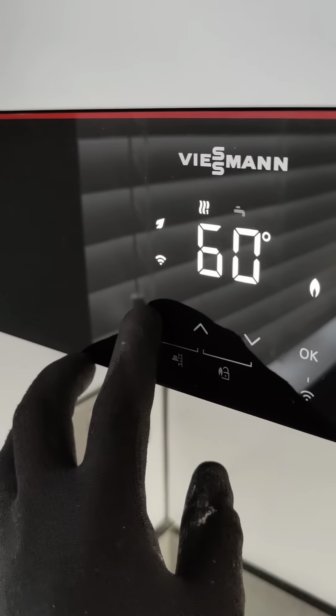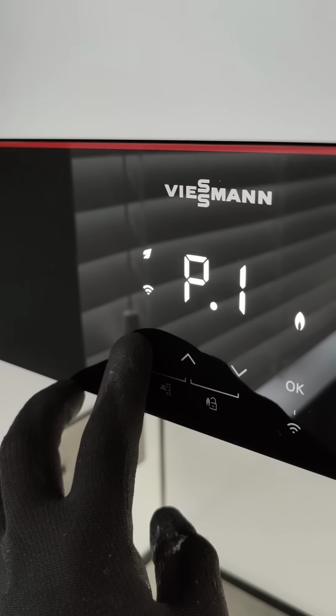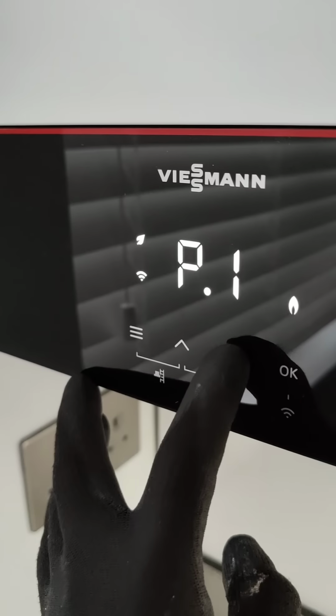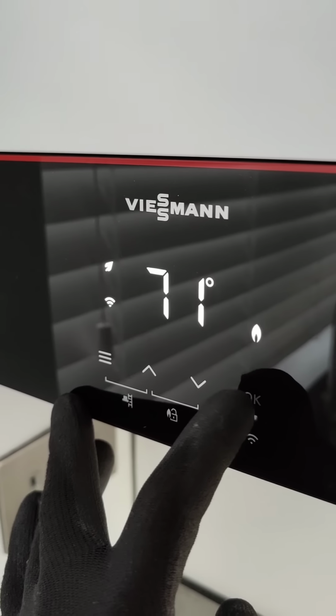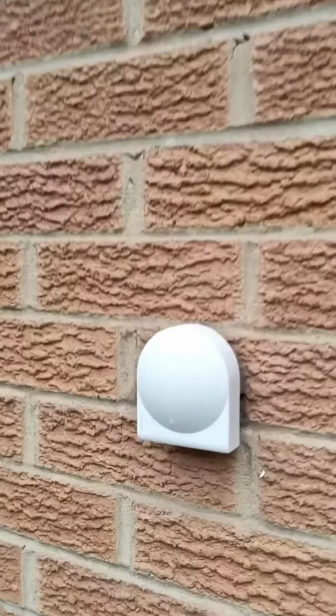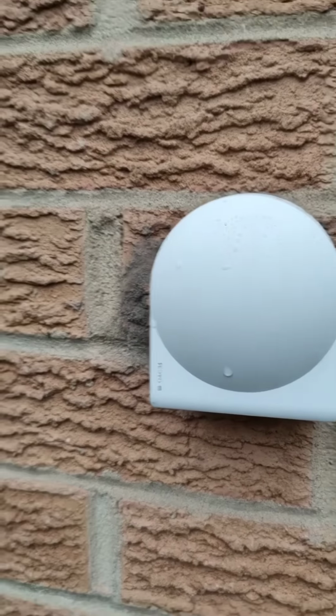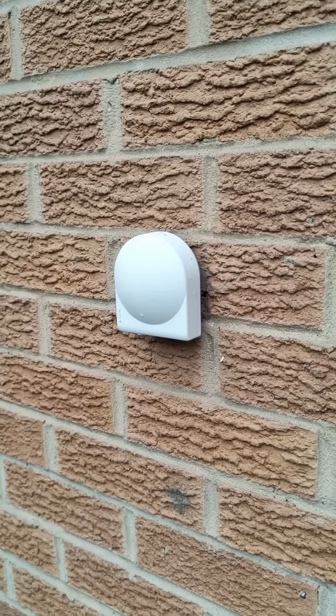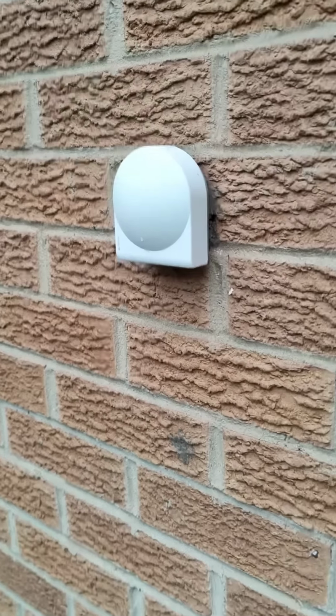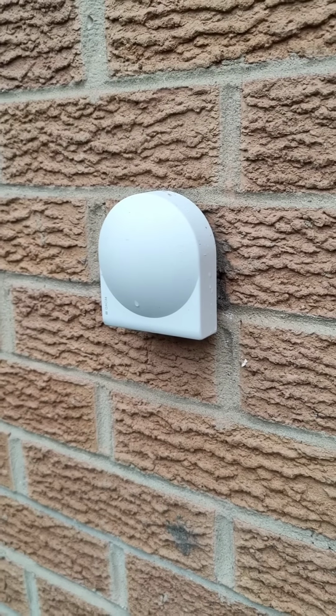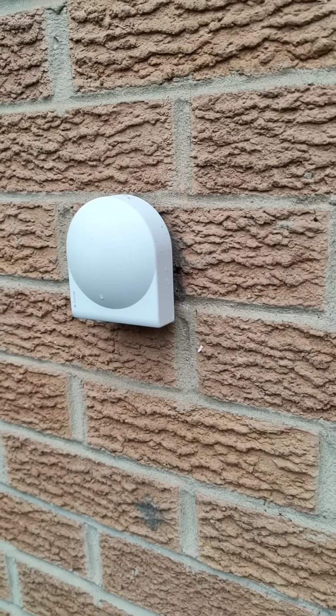We can go into the data menu, P2. So we've got the outdoor temperature if we've got a weather sensor fitted. Now this is showing 71 degrees because we've got the wrong weather sensor fitted. We fitted a 1 kilohm Siemens weather sensor which works on the other boilers like the Artex and the Baxi, but apparently you need a 10 kilohm Viessmann sensor for this boiler.